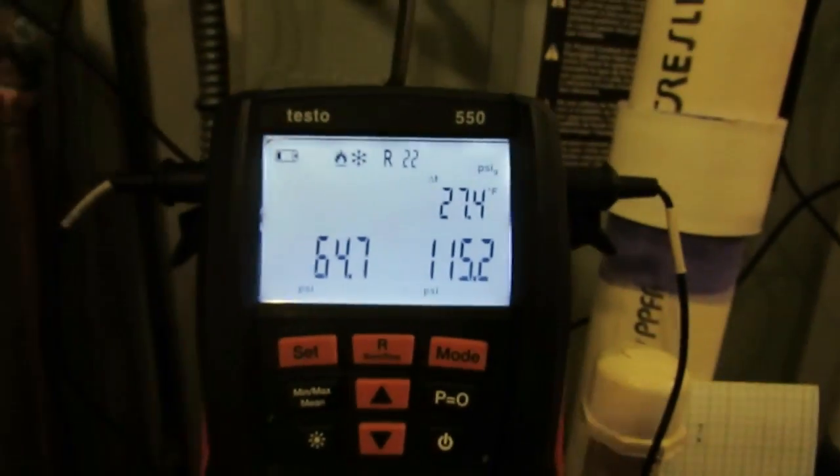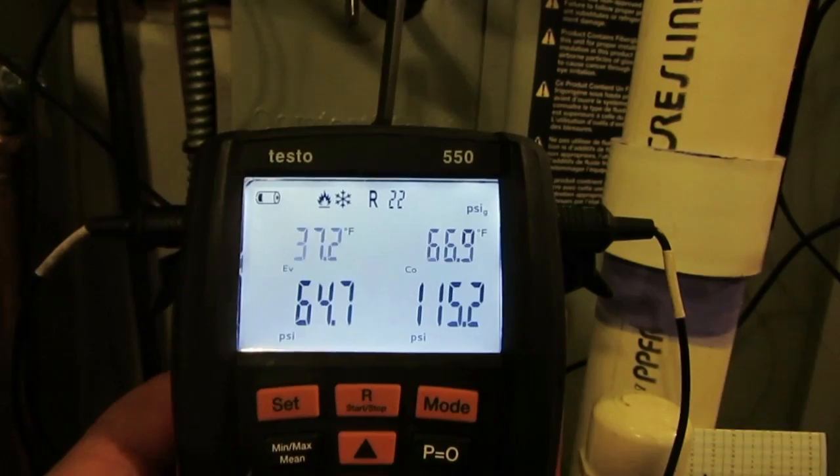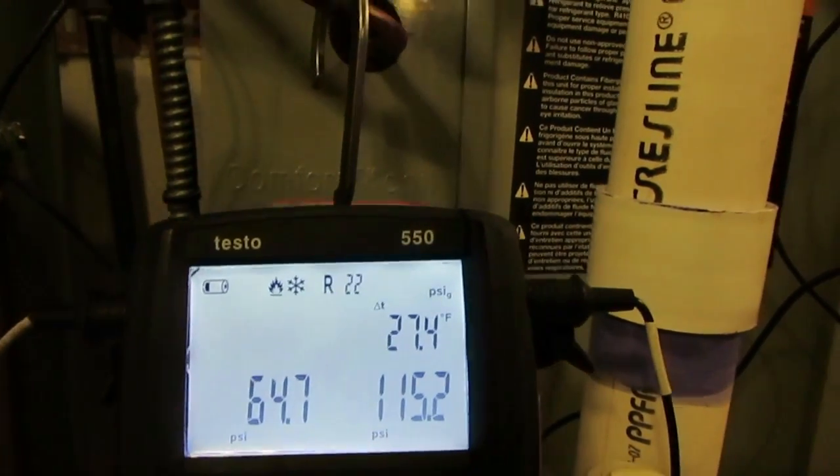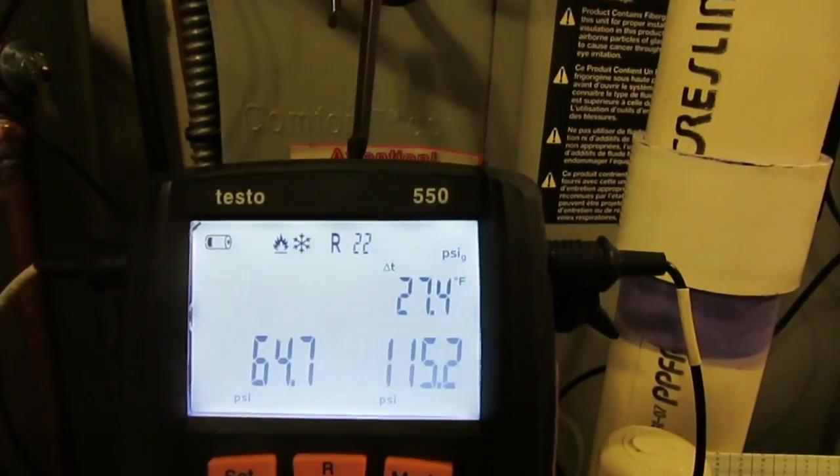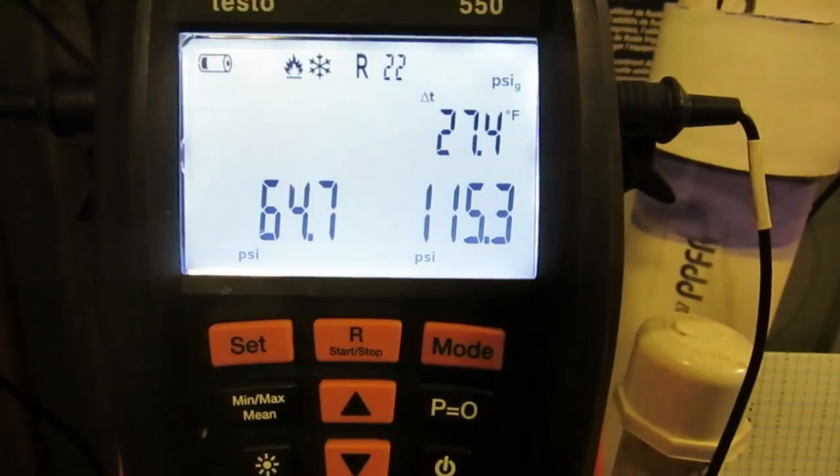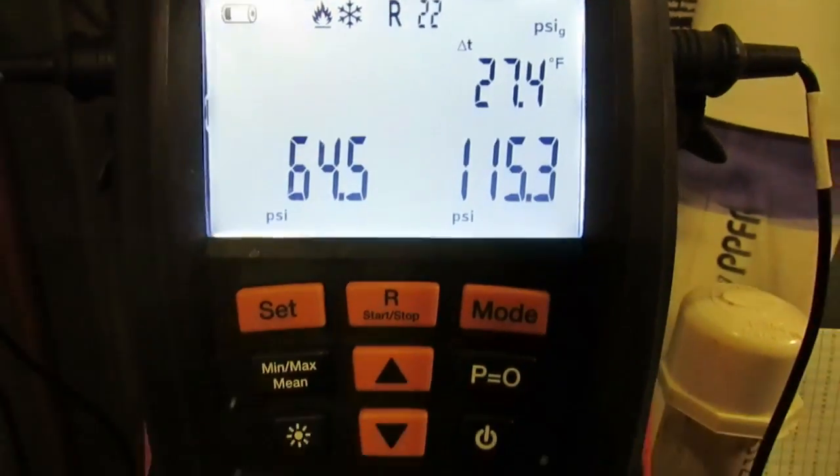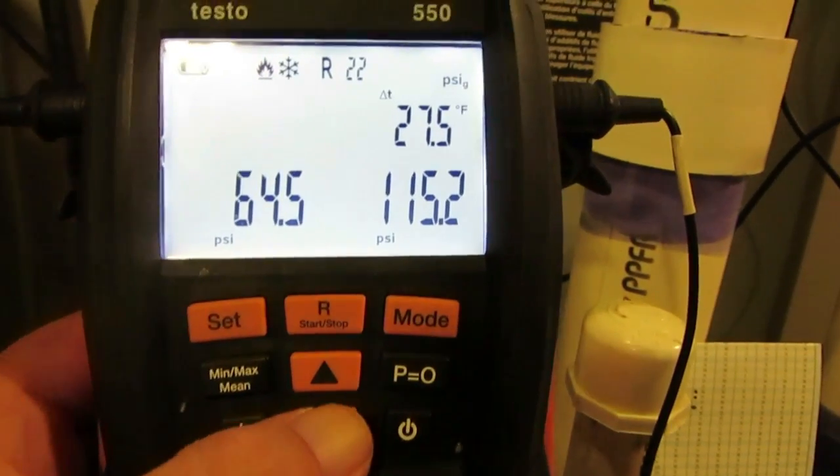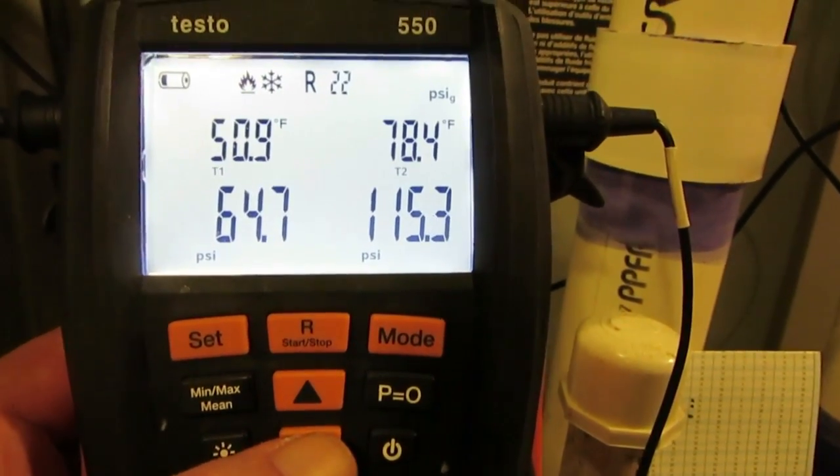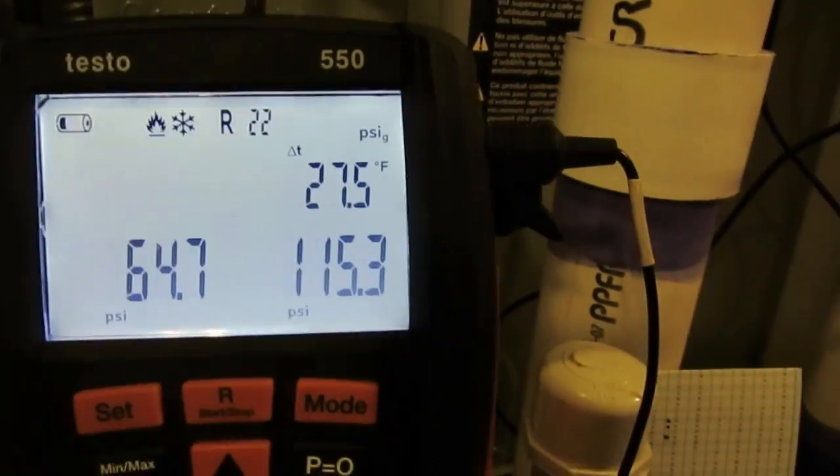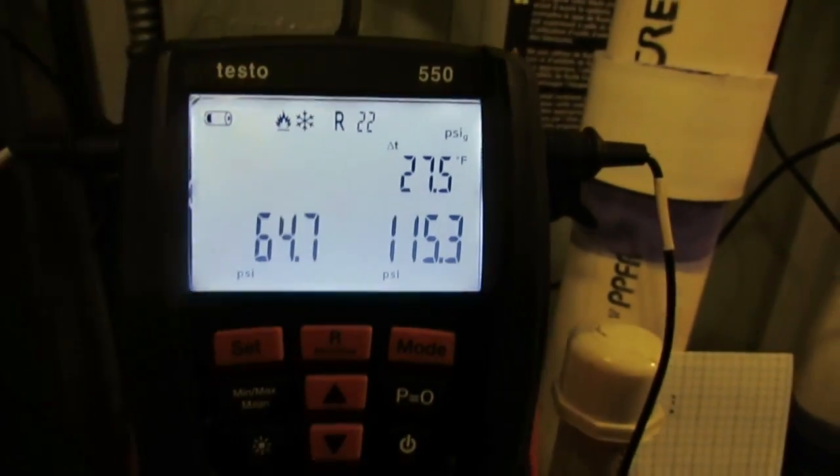Let's move on along. There's our delta T. Let's run back here real quick. What's 78.3 minus 50.9? I bet it's 28, 27.4, somewhere in there. I guarantee it's fluctuating because of the TXV, it's not going to be exact, we might be off a few points. But that's what I'm saying right there, 27.5. If we rifle back, what is it, 78.4 minus 50.9? That should be 27.5.